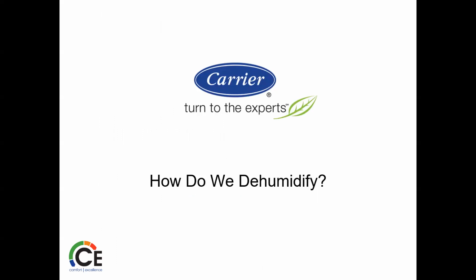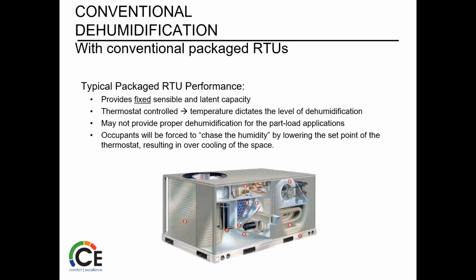So how do we do this, right? The base model rooftop without any additional things: we know air conditioning can dehumidify, but when the compressor's running, it pulls a lot out. Then as that compressor stops, we get into this ebb and flow of bringing it back in, or somebody opened the door or whatever. So there's always this ebb and flow going on. If we have a dehumidifier, we'll allow a few minutes for that cool to warm up. So then we're going to be able to do it more effectively and work through that.